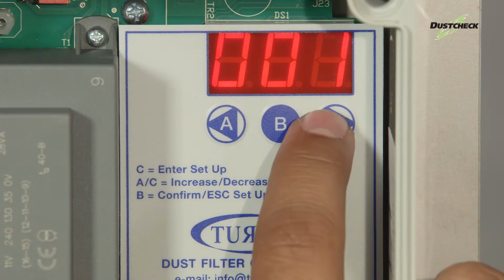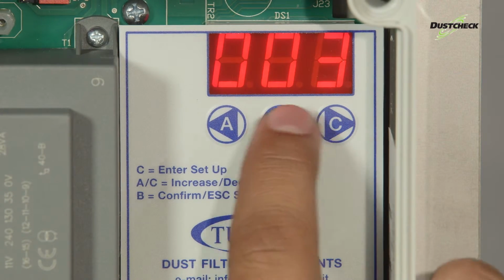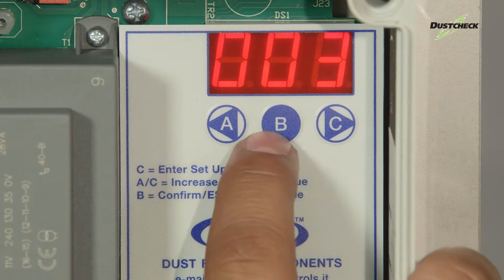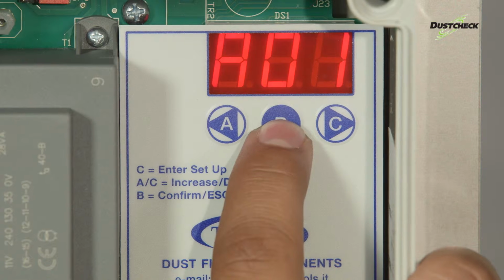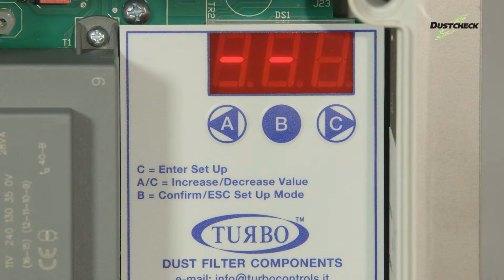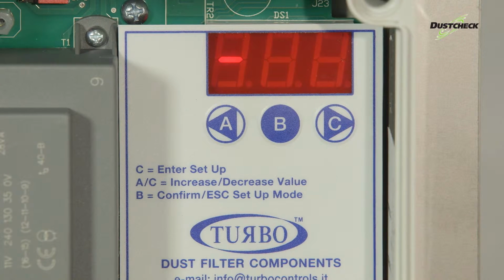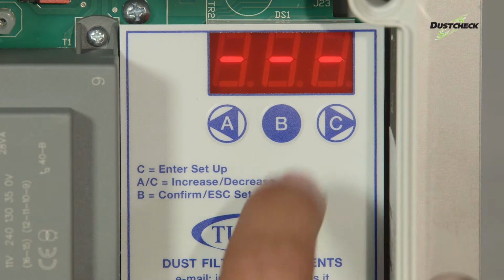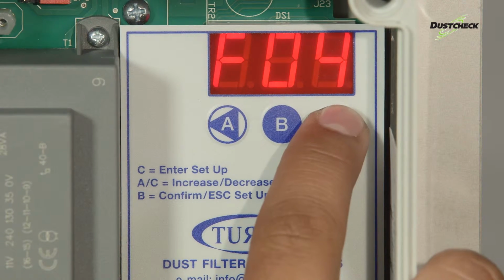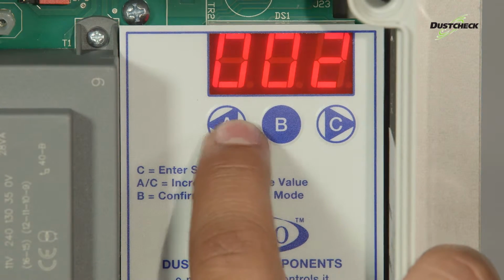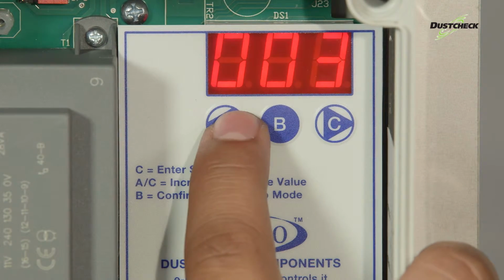Use keys A and C to adjust the setting up or down. Once the value required is displayed, press B to store the value. If you have completed all the changes, pressing B again puts the controller into operating mode. To make further changes to the other settings, press C until the desired function is displayed and A to start changes. Please be aware, the controller will revert to operating mode after 5 minutes of inactivity on the keypad.